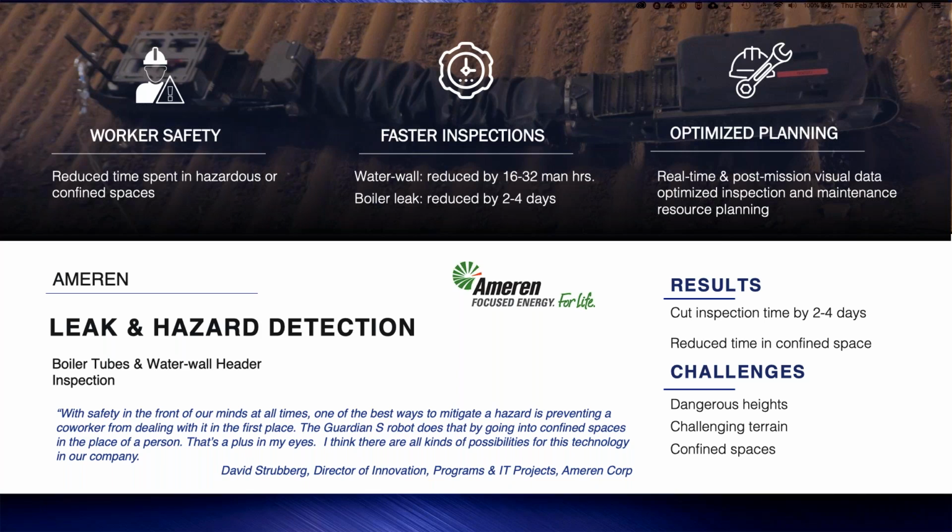So using the Guardian S eliminated the need for employees to enter mud drums, significantly reducing safety risks associated with the inspection. They calculated for us a reduction of 16 to 32 man hours needed to complete the mud drum inspections with the Guardian S. It's a major reduction. What would you do with 16 to 32 additional man hours to do something else?